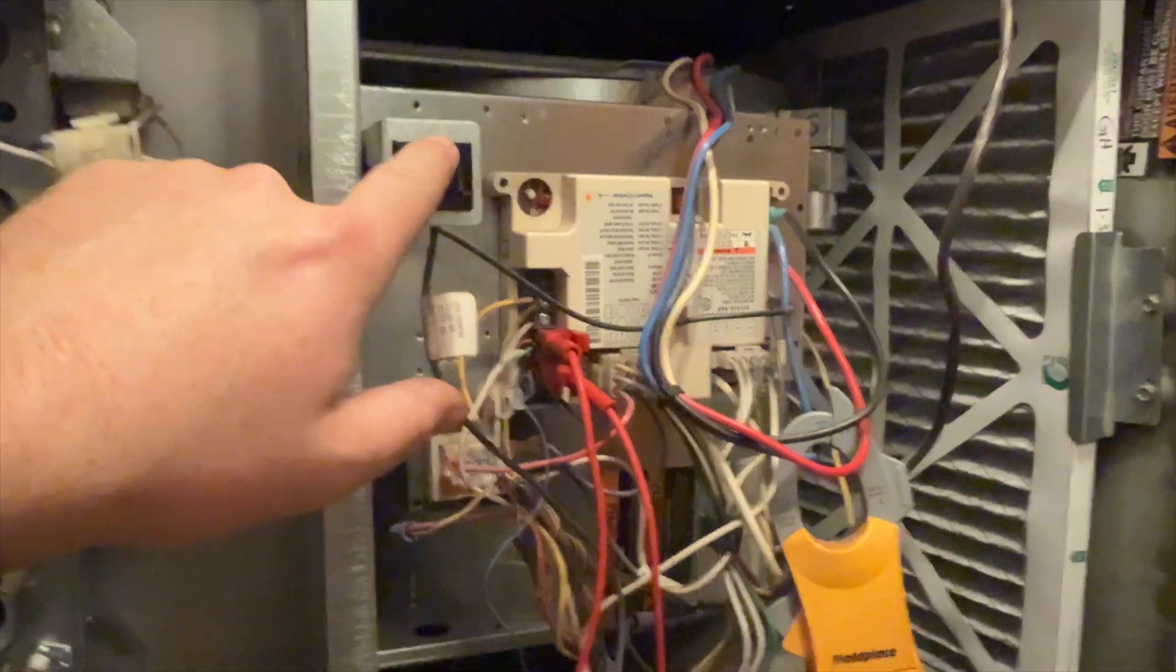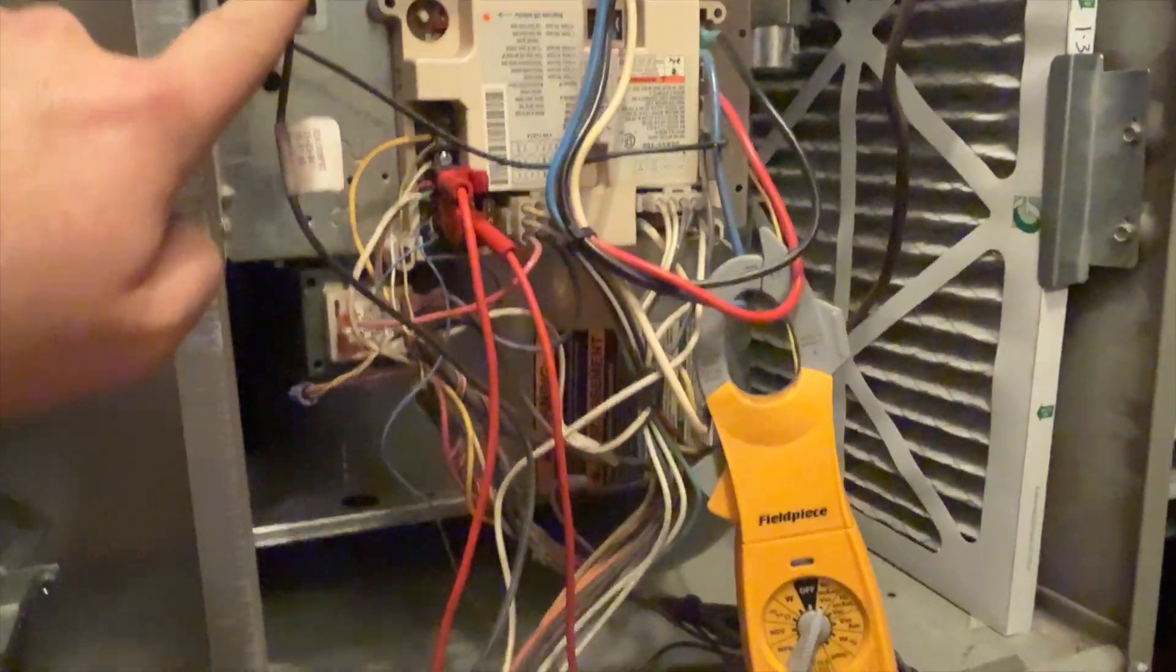Let's go ahead and cycle the fan. Yeah, the motor is definitely dead. Go ahead and check this run cap. Okay, run cap is a five, it is within specs, so it's definitely not the run cap.